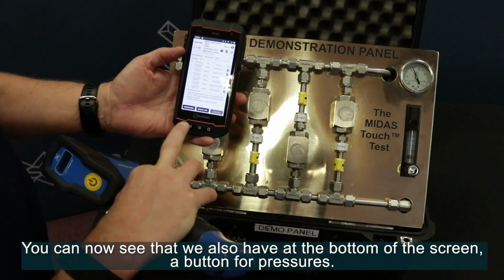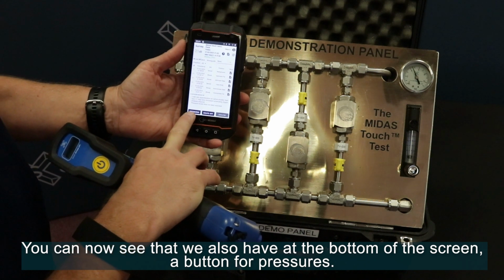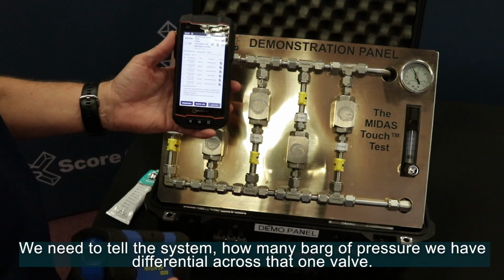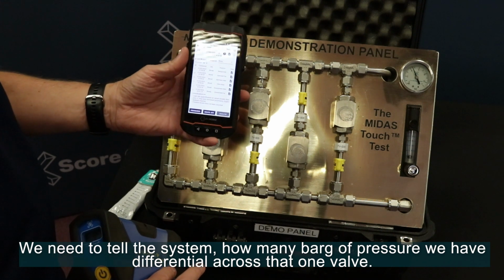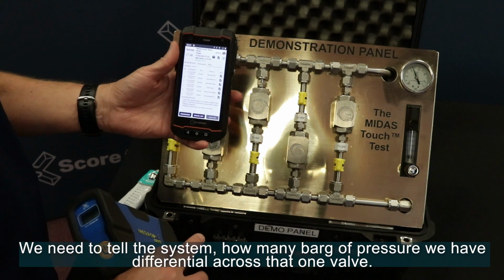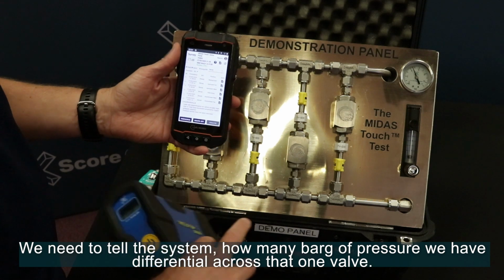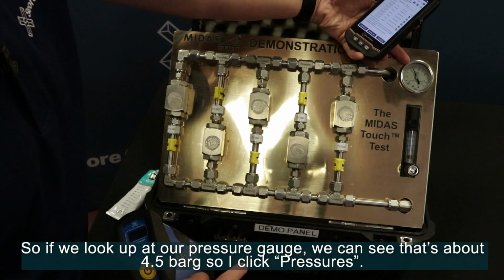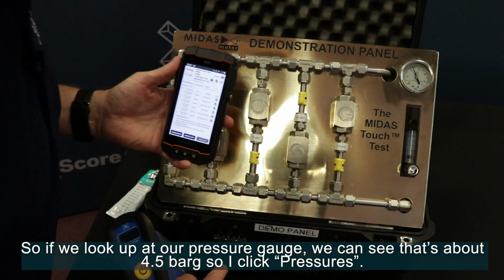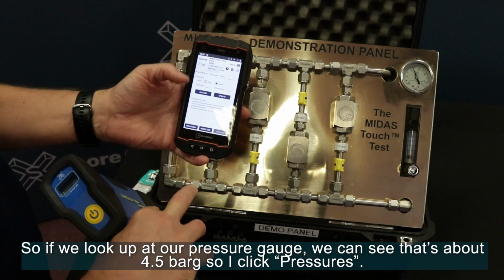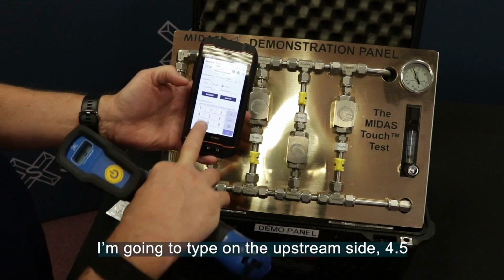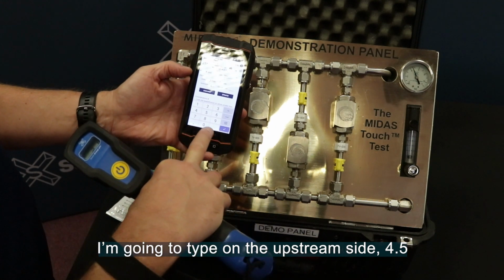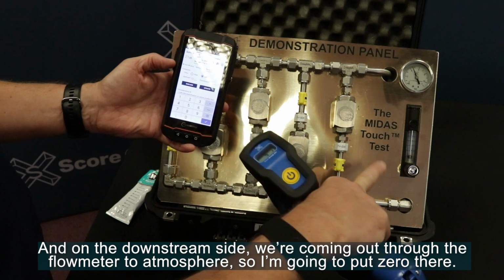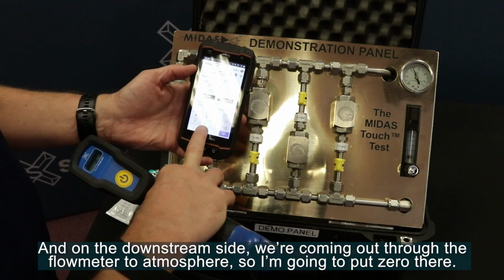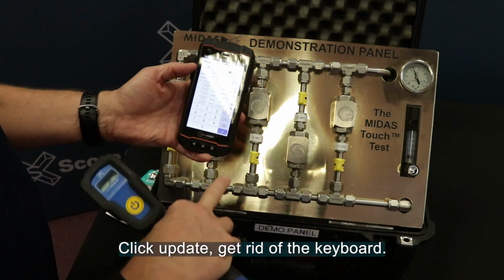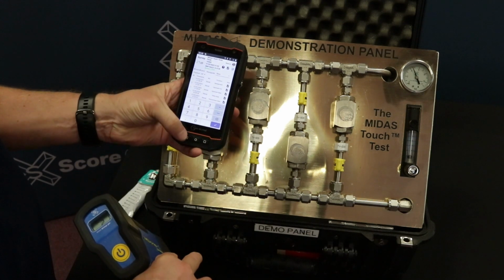You can now see that we also have at the bottom of the screen a button for pressures. We need to tell the system how many bars of pressure we have differential across that one valve. So if we look up at our pressure gauge, you can see that's about 4.5 bar. So I click pressures. I'm going to type in on the upstream side 4.5, and on the downstream side we're coming out through the flow meter to atmosphere, so I'm going to put 0 there. Click update, get rid of the keyboard.